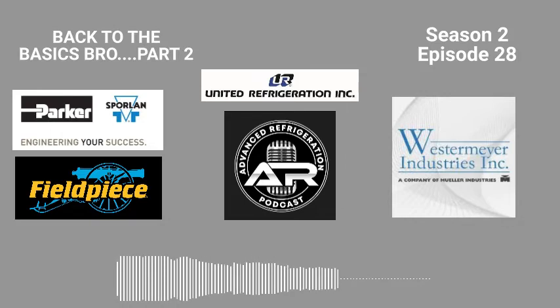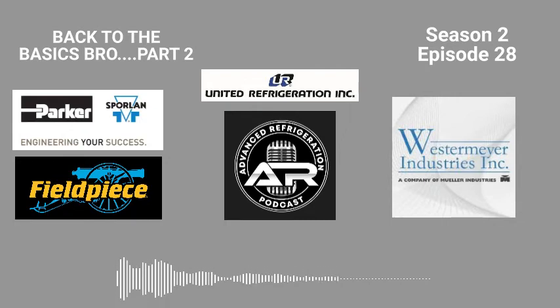But I'm also at the same time looking at the main ball valves. Where's that receiver inlet ball valve? Where's the receiver outlet ball valve? Where's the ball valves killing the store? Where's the ball valves killing the condenser? So that way, if there is an emergency situation, you know what ball valves you need to hit.